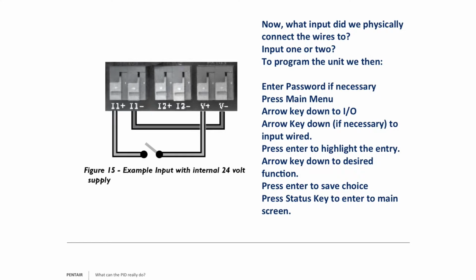So remember, when we're working with inputs, one half of the battle is to ensure that you have your wiring done properly, but the most important thing is you have to tell the drive what we intended to do once there's voltage applied or no voltage. Okay.